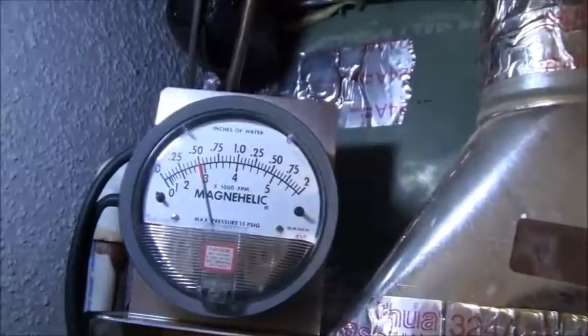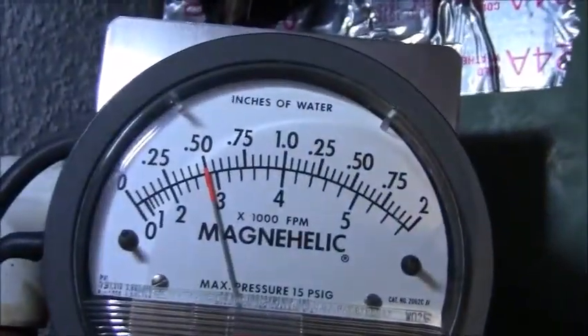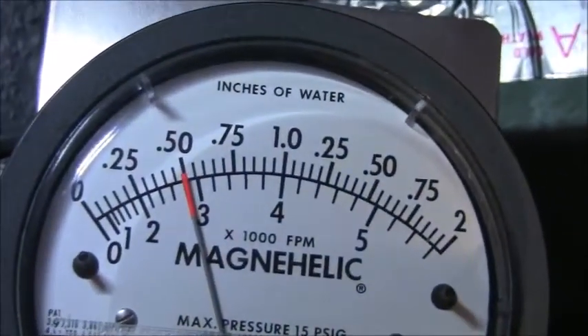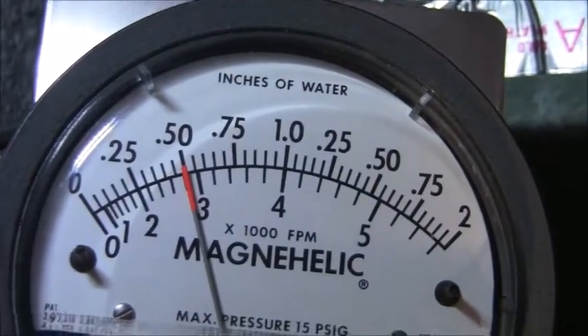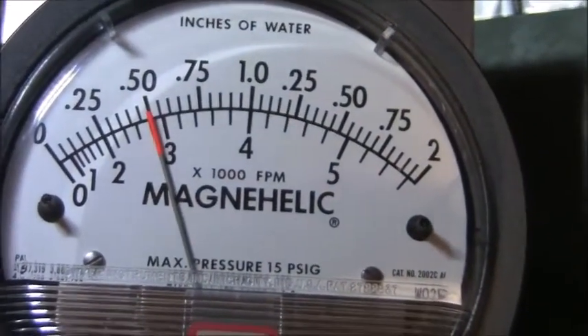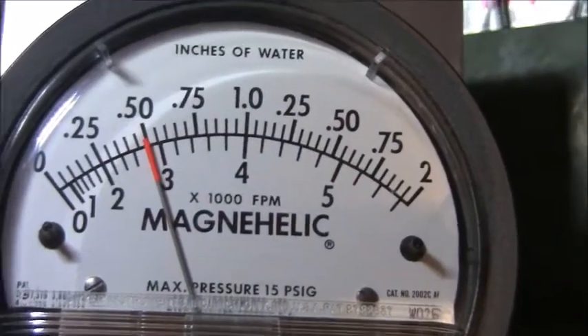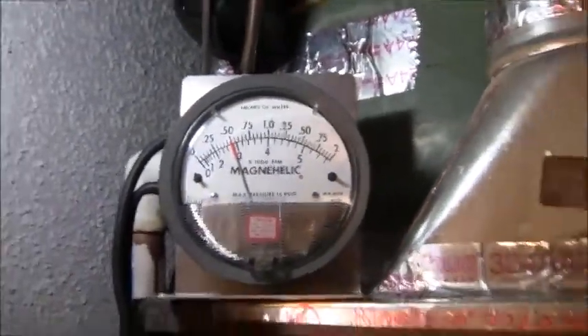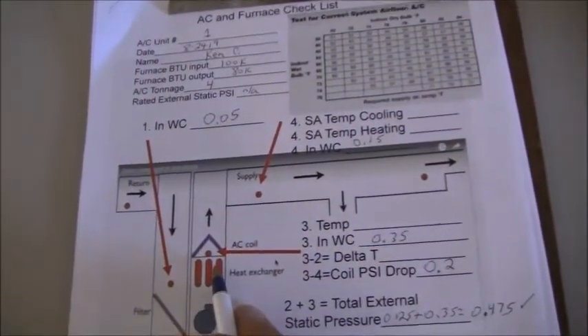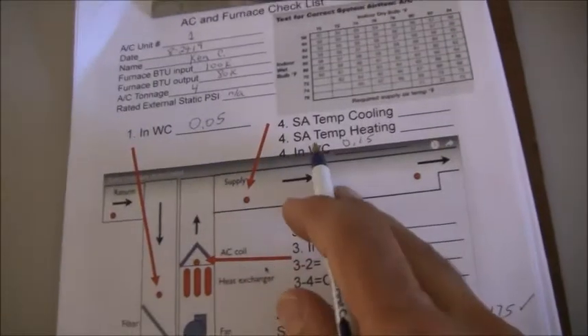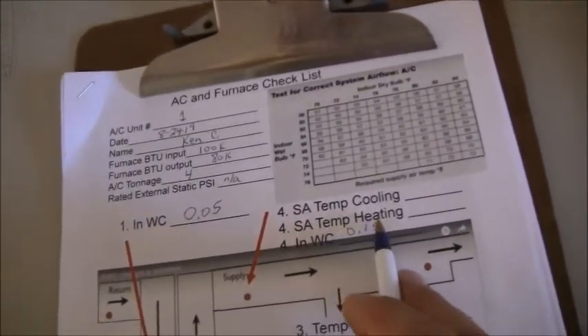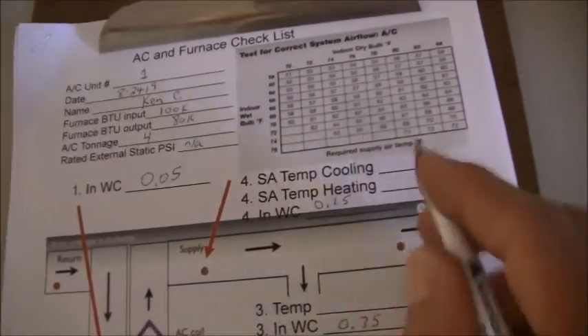There is your external static pressure on the magnehelic gauge. That is at 0.5 inches, a half of an inch of static pressure, water column. That is a good static pressure. This unit is breathing, and it is allowing the proper amount of airflow with the fan in heating for CFM. All right, the supply air heating temperature was 147.